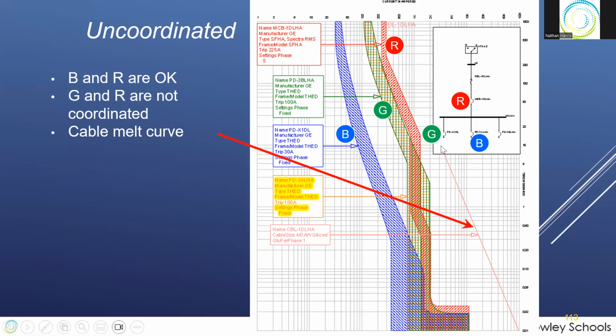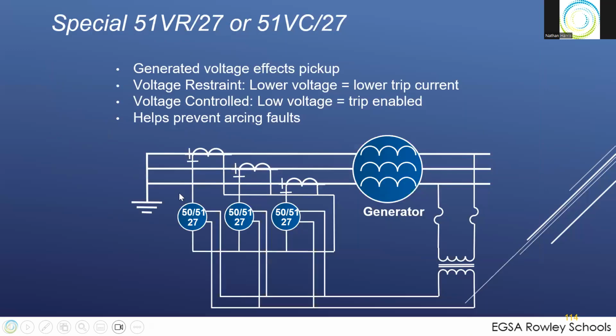Otherwise, if we have a problem down here on the green feeder circuit somewhere, you'll trip the main breaker before you trip the feeder breaker. You don't want that, obviously. Arcing faults, like we saw up front, you want to prevent that.